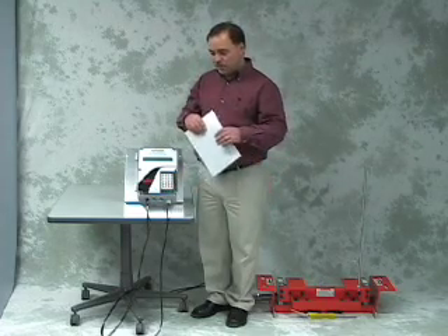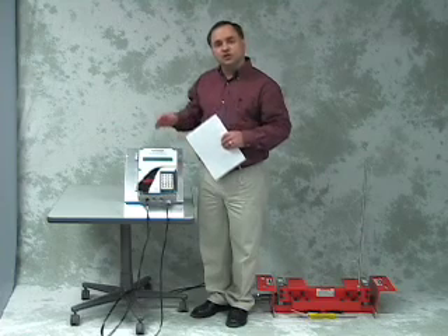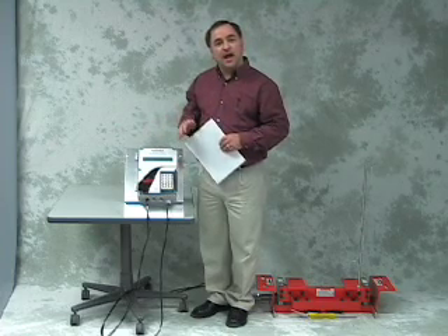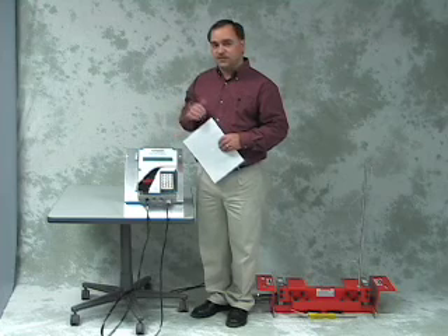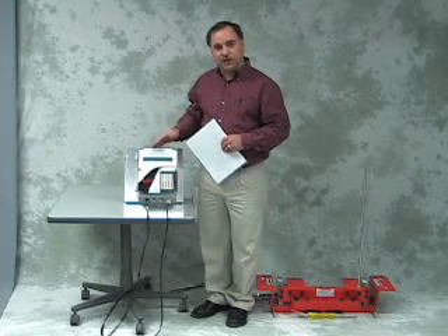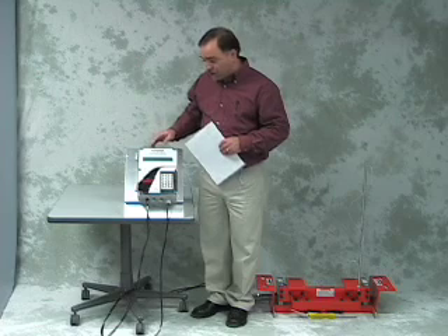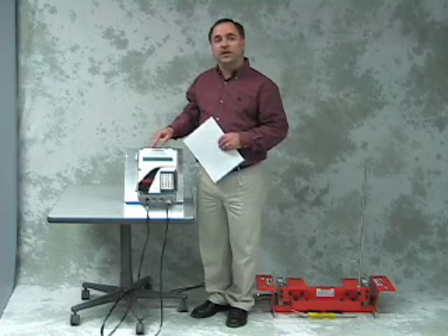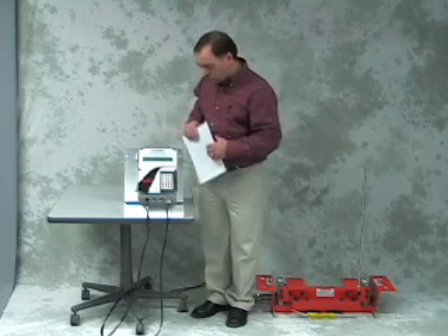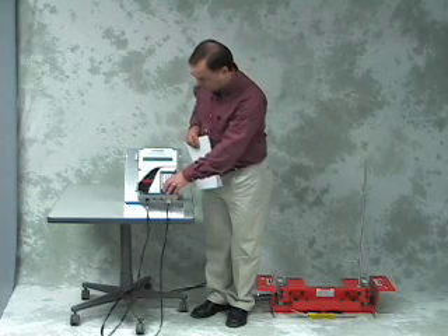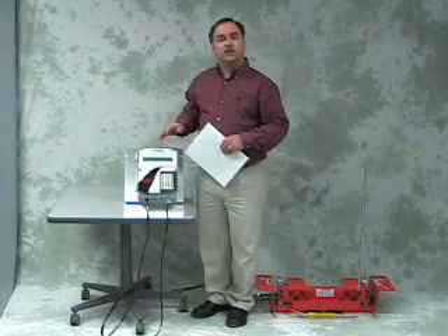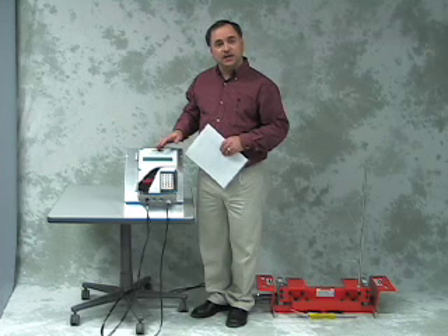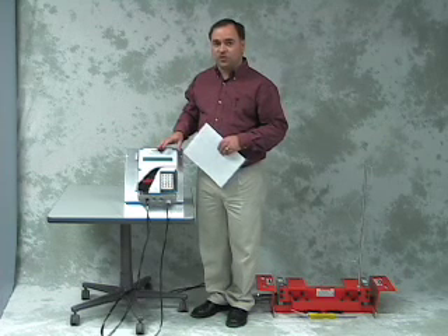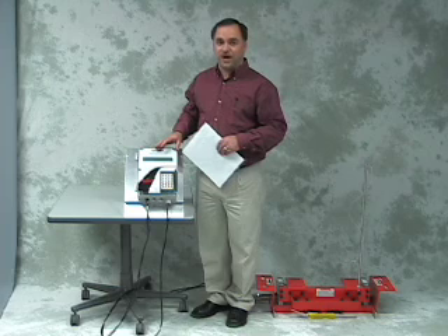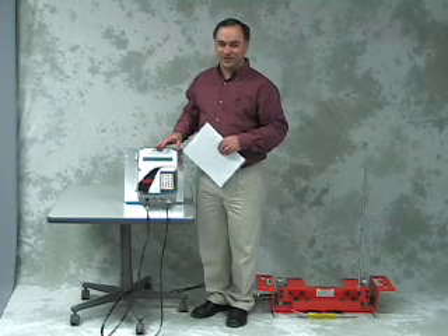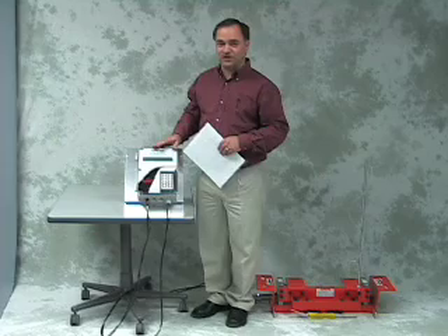The calibration parameters that we have set up for you are showing this belt scale as a bathroom scale. We can stand on that and see our weight displayed on the display. The rate display is set up to read your weight in pounds. The load display, by pressing the Alt display key, we can see the load display. The load display is set up to read your weight in kilograms. Everybody in North America knows how much they weigh in pounds. The rest of the world knows how much they weigh in kilograms. So we have both displays available.